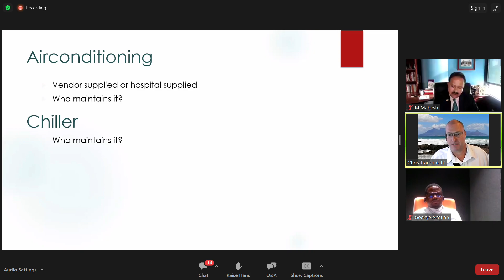The chiller for the LINAC, who maintains it? Again, this kind of stuff could go into the specifications, may apply to you, it may not apply. You got to think about licensing. Do I need permission from the regulator to import a LINAC? What of this is my job? How much of this is the vendor's job? And what's the time frame for this? So this isn't necessarily going to go into the specification document, but it's something that you should be aware of. So it's not just the LINAC that we're trying to specify.